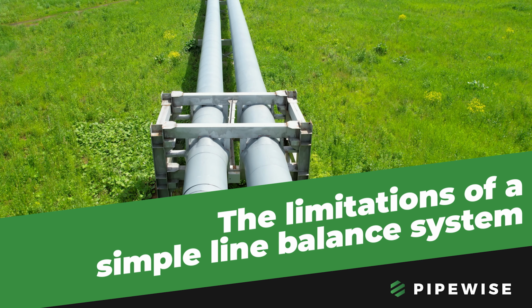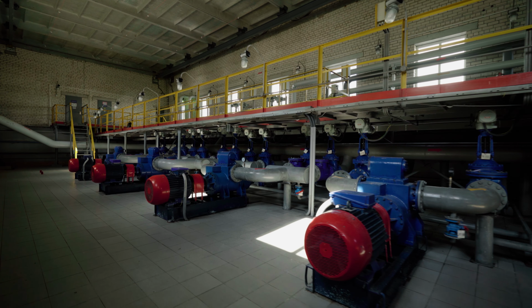What we see a lot of the time is that they'll take their measurements and they'll try to do a fairly simple volume balance, comparing the flow that goes into the pipeline against the flow that comes out of the pipeline. And if there's a deficit there, then that's probably indicative of a leak somewhere along the pipeline. But there's all sorts of real world complexities that arise when you start implementing that, things that aren't necessarily obvious on the surface. How do you deal with startups and shutdowns or transients or pump speed changes and stuff like that?